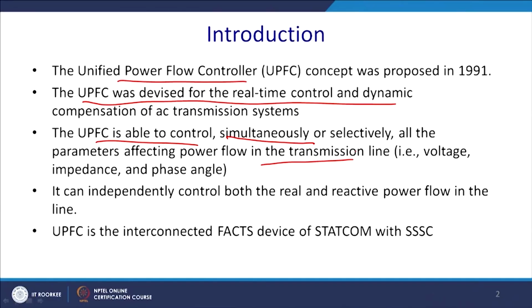It can independently control both the real and the reactive power. Active power cannot be controlled by the shunt compensation, and the same way for voltage regulation. Series compensation is better in that way because it can control the flow of the active power. But series alone cannot independently control the flow of active and reactive power. Here it is possible to decouple the flow of the active and the reactive power by this UPFC.